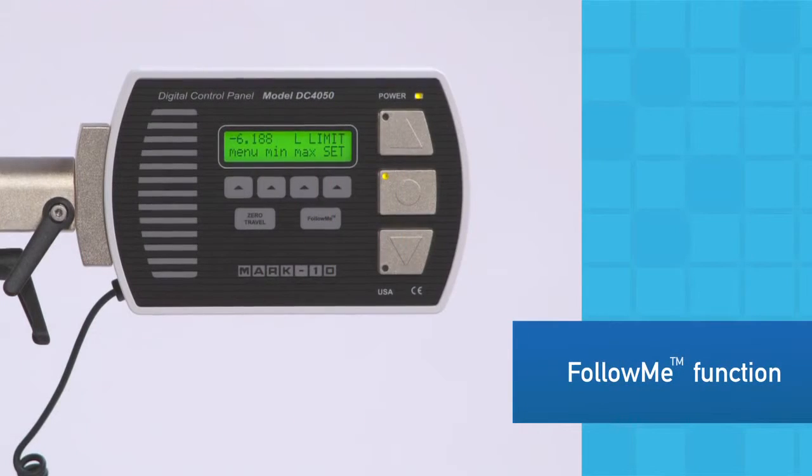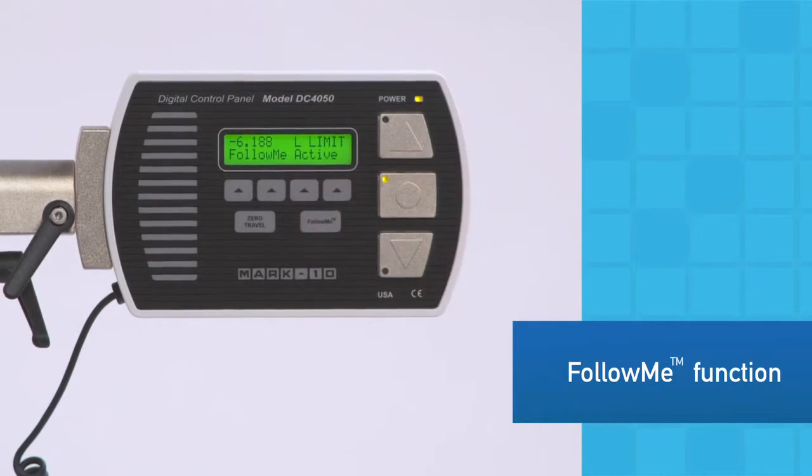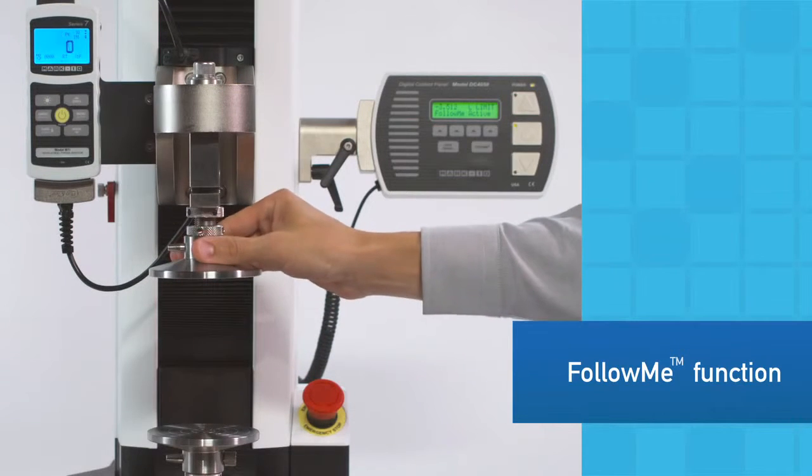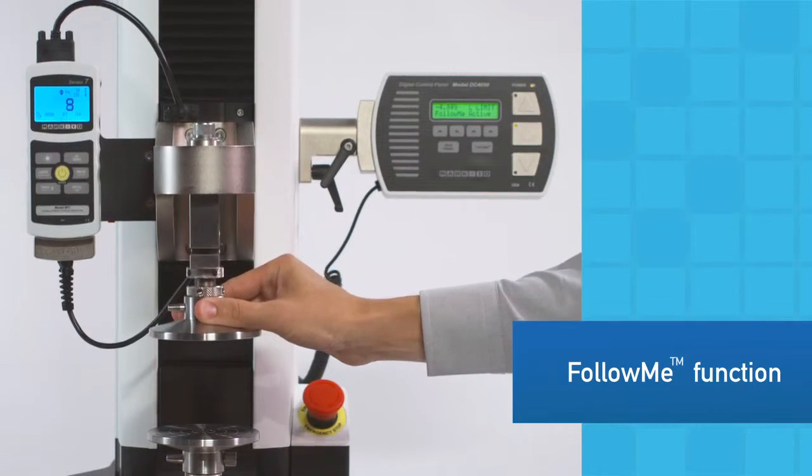Easily position the crosshead for sample setup with the unique follow-me function. Simply push and pull on the load cell or force gauge to move the crosshead. The greater the force, the faster the speed.